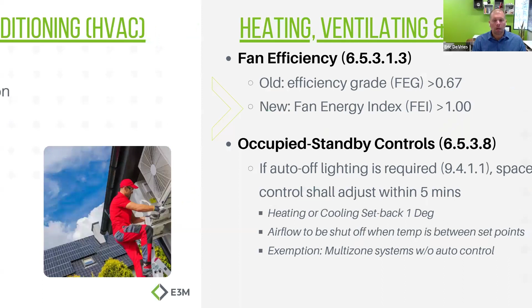Another big change, this pertains to maybe if there's a manufacturer on this call or if anybody that's speccing exhaust fans. You used to spec everything on a fan efficiency grade, FEG. That essentially rating is being obsoleted. Everything will now be rated under fan energy index. So what that does, fan efficiency grade, an FEG, really looked at the motor itself. Well, the code officials started to realize you can have a really efficient motor, but you put a terrible belt and a terrible fan blade on it. You put other components with it, you actually can lose the performance. So fan energy index, FEI, is now a measure of the entire assembly, the belts, the bearings, the fan blade itself, the motor.